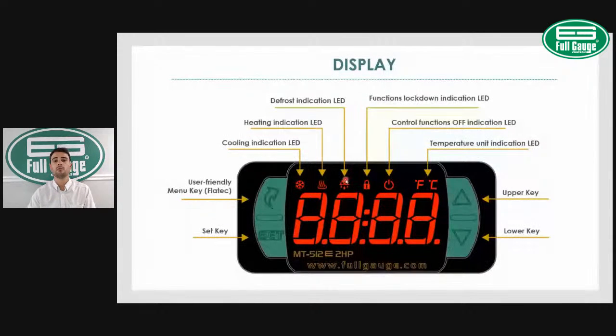This is good because I've seen a lot of guys that get a call from their customer saying, "Hey, my unit is not keeping a good temperature. My cooler is too warm." And the first question you have to ask your customer is, is there a defrost LED icon lit in there? If the defrost LED icon is lit, that means the controller is performing the defrost cycle and the temperature inside of the cooler will definitely be warmer. That's an indication.